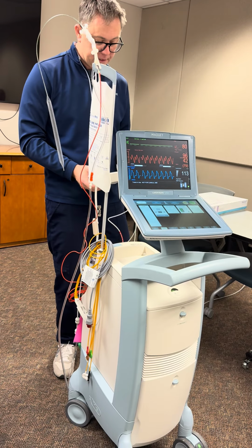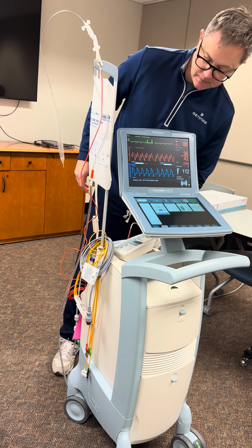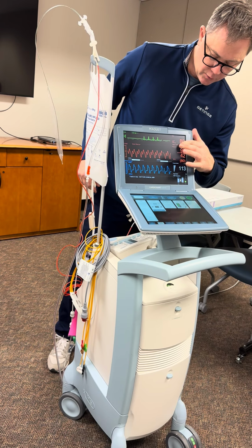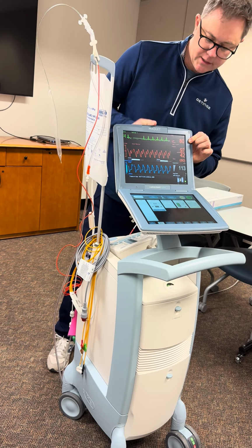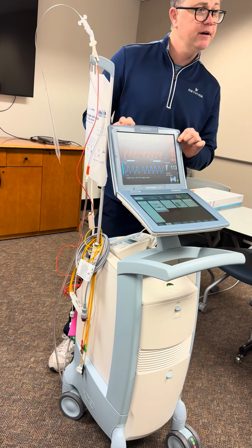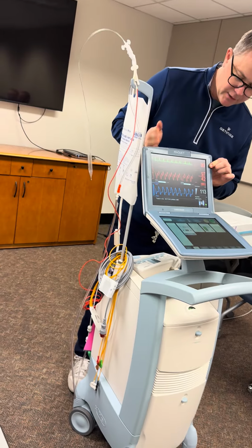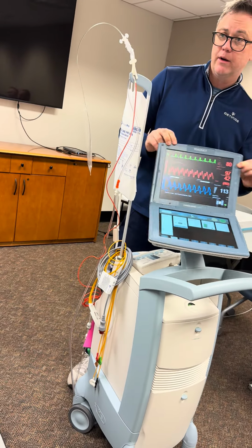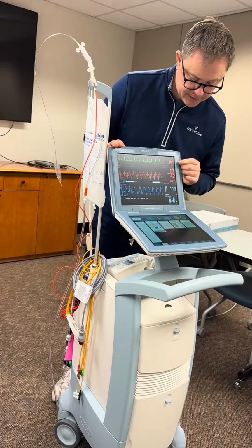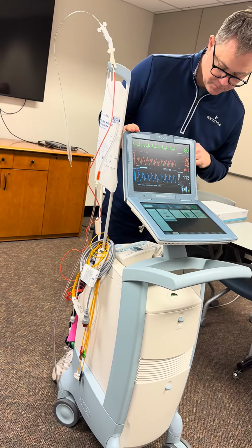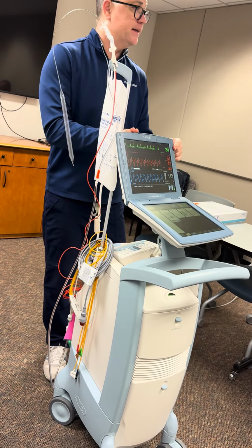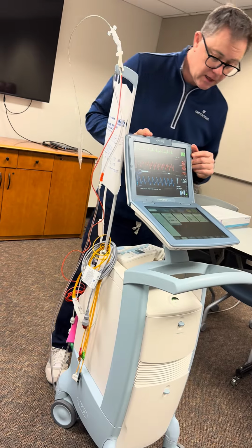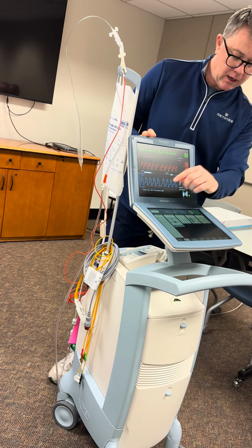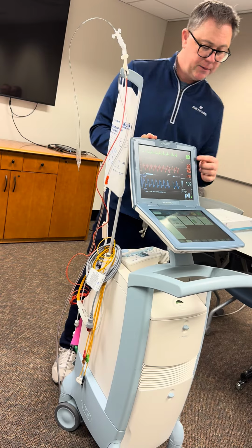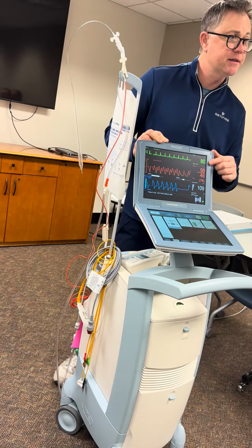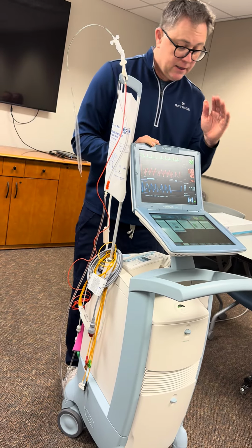Once we're able to get the leads back on the patient, so right now it's red and it's telling me we're in the pressure trigger. It wants to make sure it's got a good reliable R wave here. And then once it says, okay, I trust that we have a good reliable R wave, it'll switch back over to that ECG. This will turn green. There we go. So now we're back in that ECG trigger. When you hit start, it puts you into the auto mode, and it's gonna go between these two triggers based on whichever signal's the best.